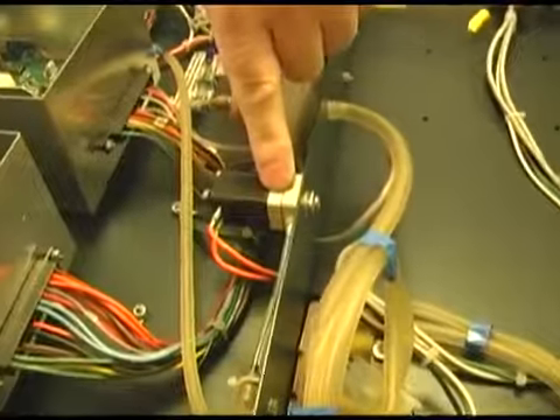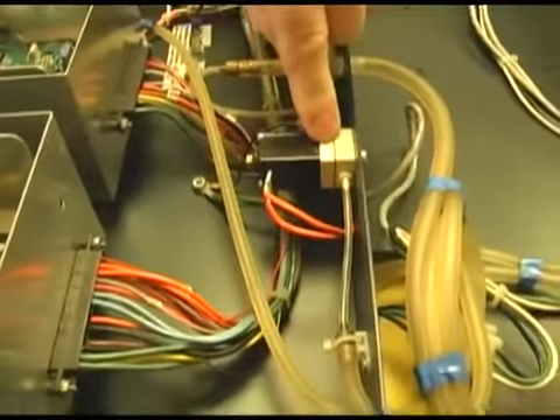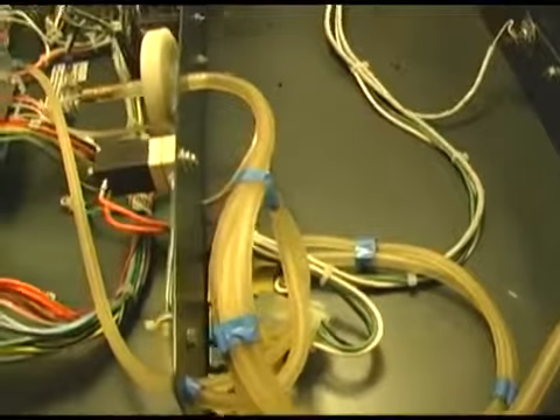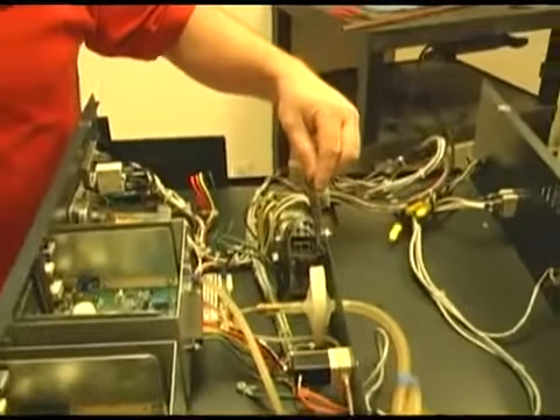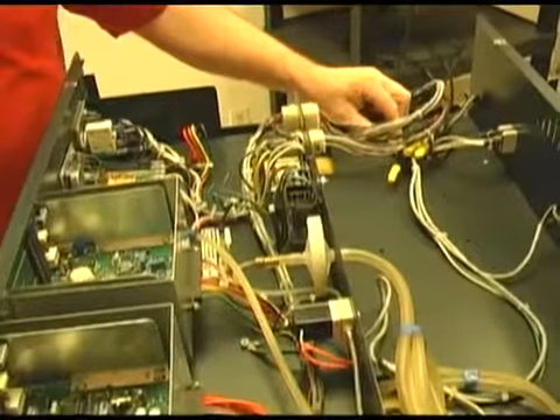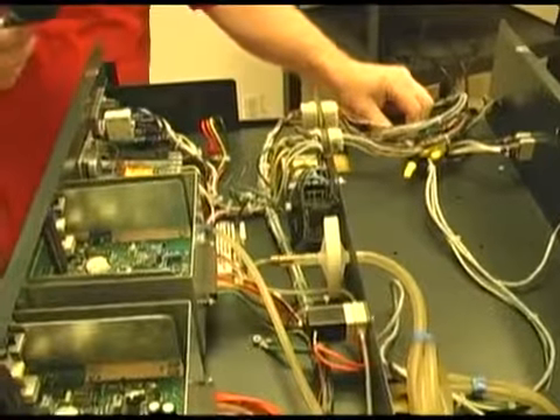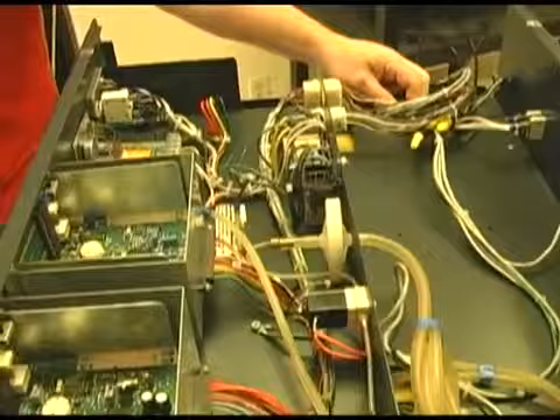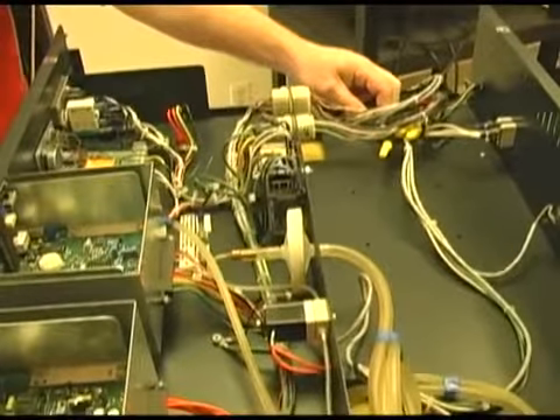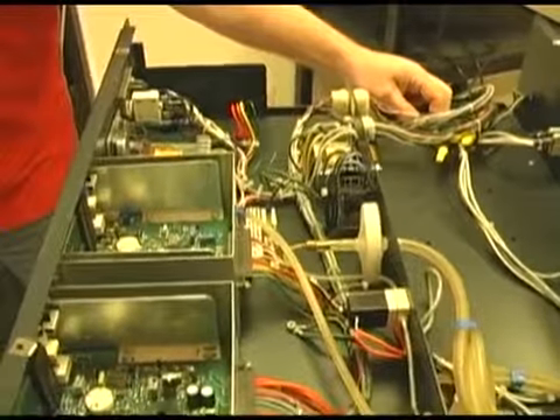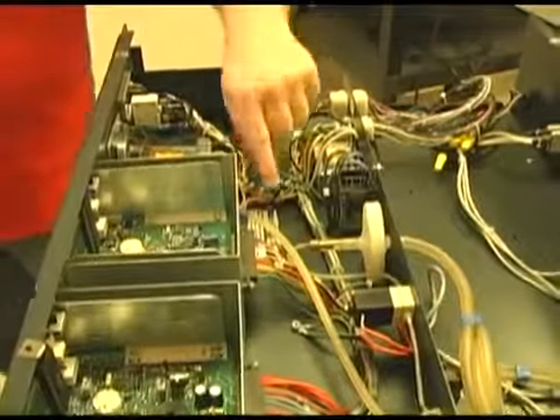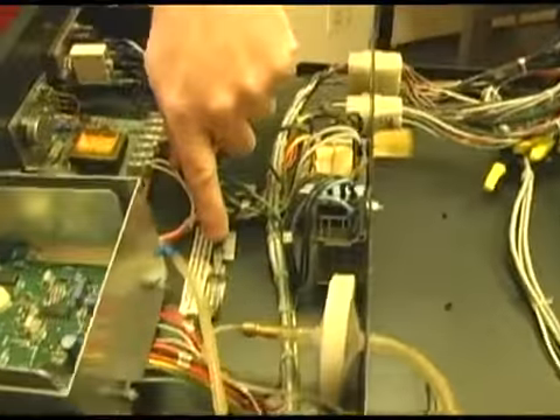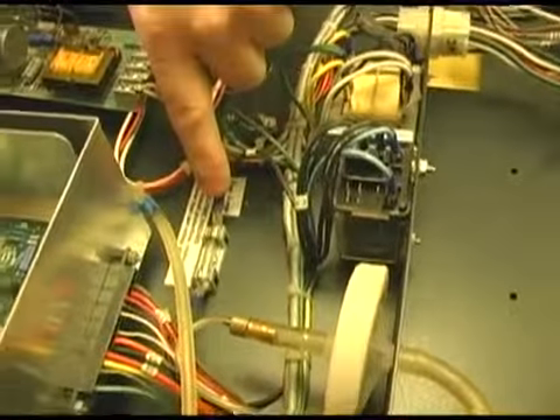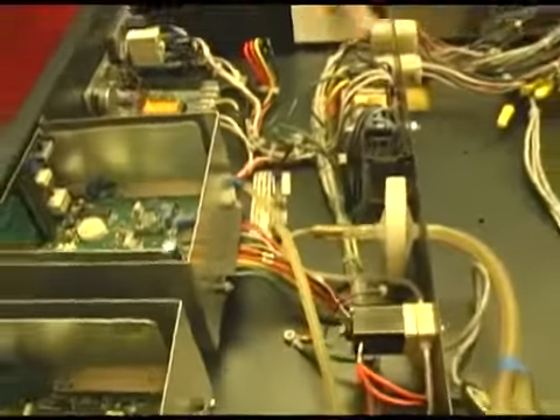This is the incoming line coming from your CO2 tank. It goes to an inject solenoid. This is very common. Almost all incubators have an inject solenoid, and this is what controls the CO2 going out to the chamber. Also, this has controls on here, and it's pretty much an AC fan. That fan has to run all the time. It is what circulates the CO2 inside the chamber, and that's very common to most incubators. They all have some way of circulating that air. Many of them have fans inside, as an example like this one. Oh, and let's not forget to mention the fuse. The fuse goes there to protect from high voltage spikes. And of course, if you see no displays at all, that's where your problem more likely is.